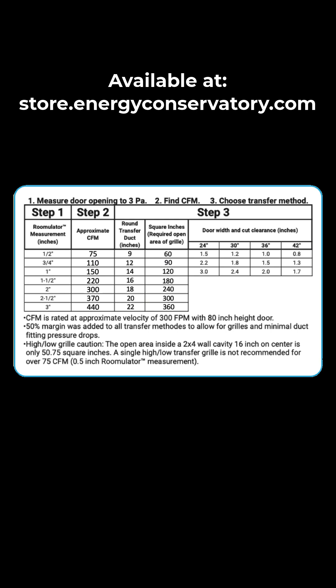As we flip the card over and follow the process from left to right, we can see that we have just completed Step 1 — measuring our door opening to three pascals with an opening of one and a half inches. Step 2 lets us know the corresponding CFM needed for transfer.